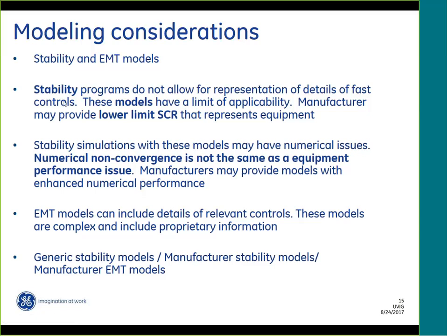That doesn't mean stability models are useless, it means they have some limits on when they can be used. In general, stability models can be used to understand these problems up to a certain level of short circuit ratio. What you may find is that manufacturers or the entity issuing a model will provide a minimum value of short circuit ratio where the model can really represent the equipment.